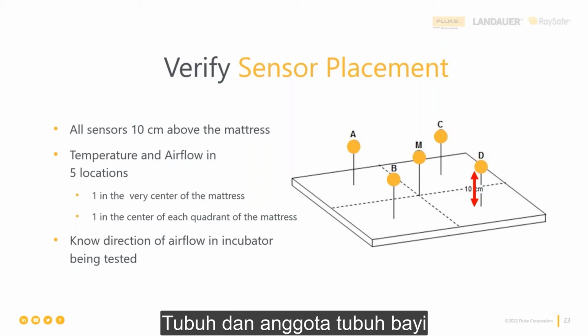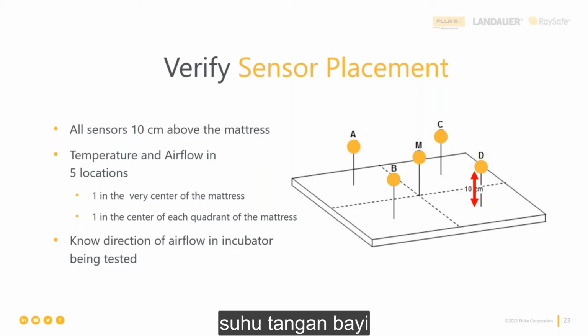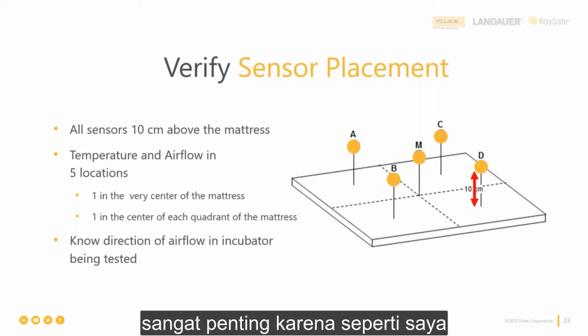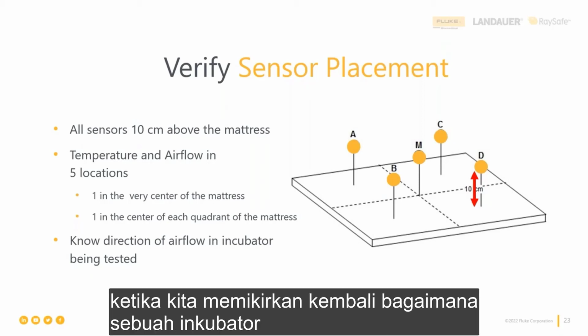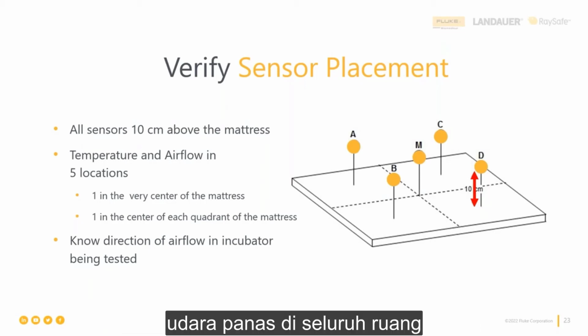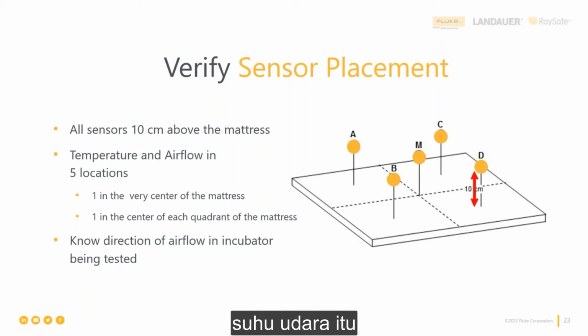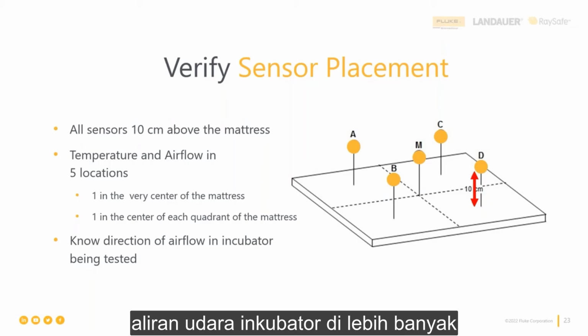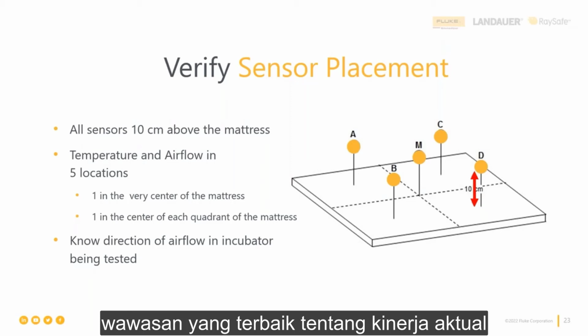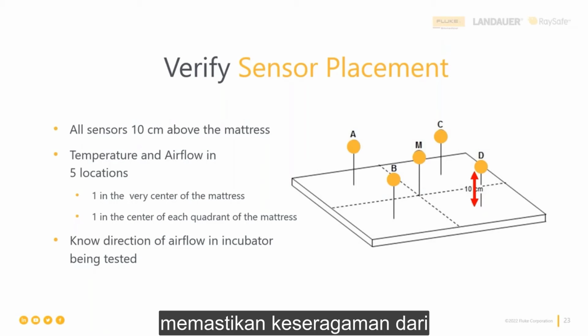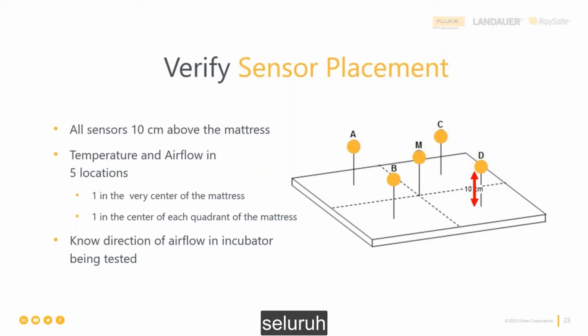This should make sense as an infant's torso and limbs may be stretched across more than just the very center of the mattress. Or you might only be getting the temperature of what the baby's hand might be experiencing while missing what their foot on the other side of their body might be experiencing. So we really need to ensure that the environmental conditions are uniform across the entire chamber. Maintaining an infant's core and skin temperature is absolutely critical, as I've said before. And as we think back to how an incubator functions, you have a motorized fan that circulates heated air throughout the chamber of the incubator. Heat loss from the infant by convection is dependent upon that air speed and that air temperature. So by measuring both the temperature and the airflow of the incubator in more than one location, you'll get a really good insight into the actual performance of the medical device, and you'll be ensuring the uniformity of those environmental parameters throughout the entire incubator.